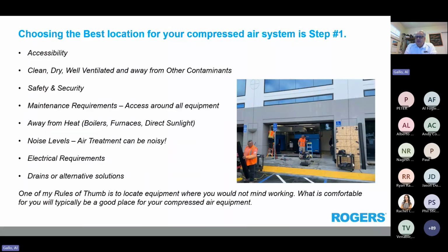that. So just be mindful, figure out where that needs to go, because then now the electrician needs to know, hey, I need to bring 460 volt wiring over to this corner of the building. And the HVAC guy, oh, I need to provide heating and cooling over there and so forth. So just kind of keep that in mind. And also, are there drains for the condensate that we are pulling out of the air system? Does it have a place to go after it's going through the water separator?